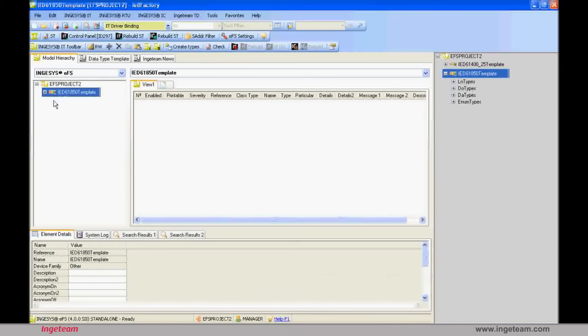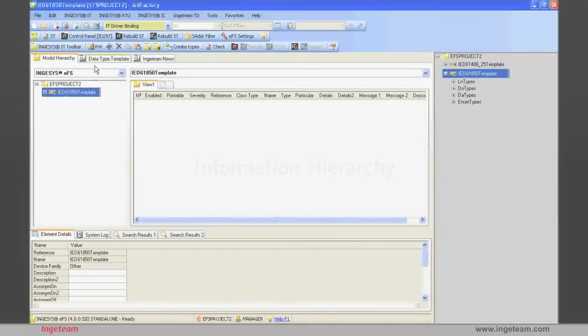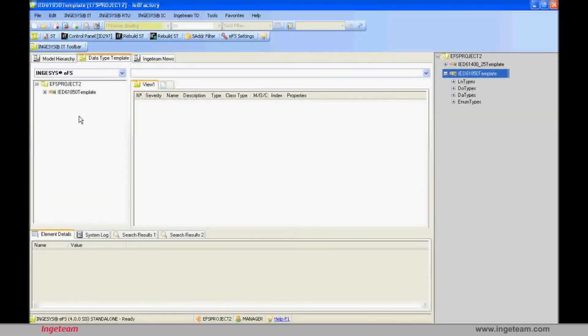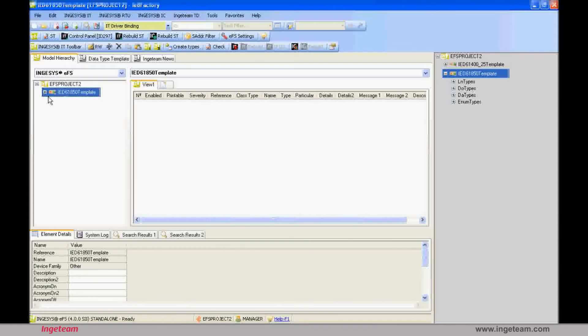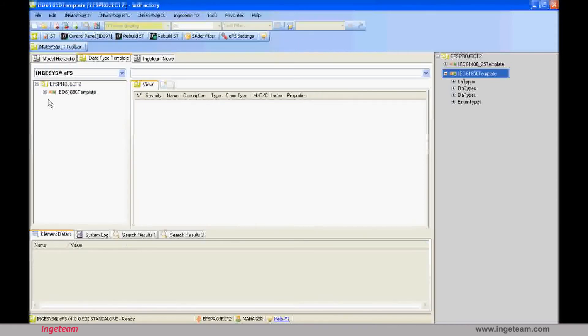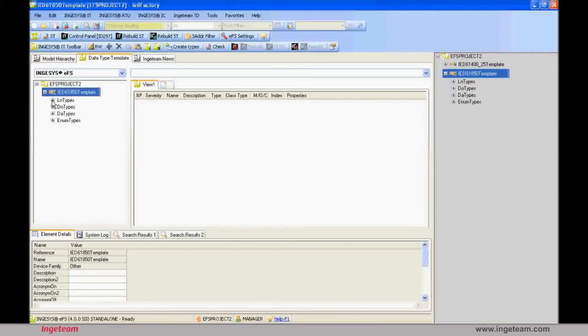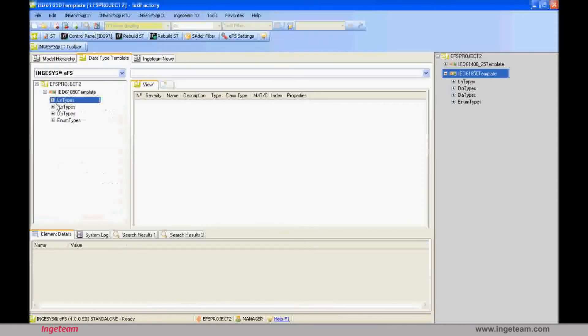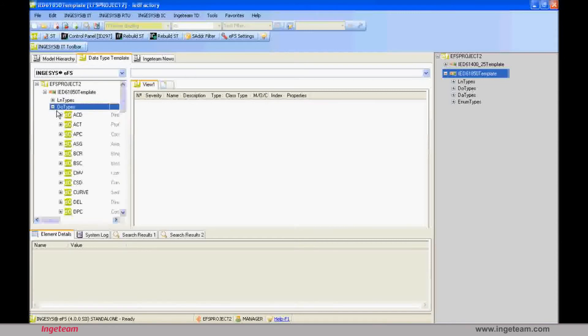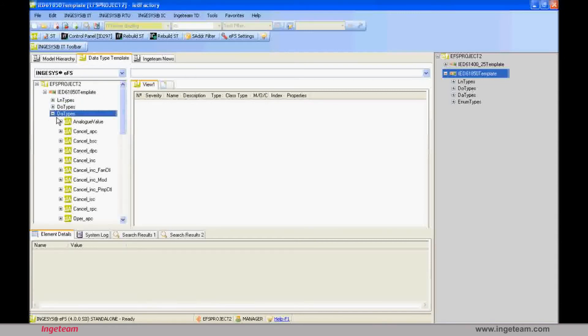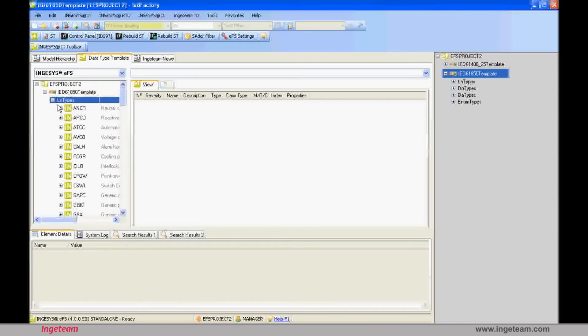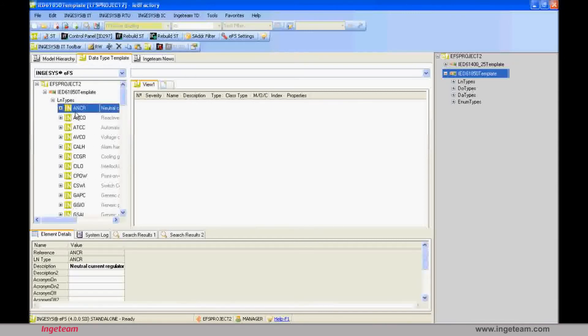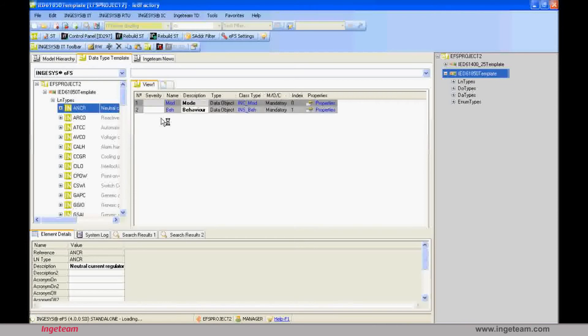Each device has an information hierarchy, in other words, the information model that it is going to use as well as a set of classes and sub-classes on which it is based. In the case of the standard, the hierarchical model is empty given that it is not a real device, and for the moment, we only have the classes available to make its model. These classes are divided into logical node, data object, and data attribute.